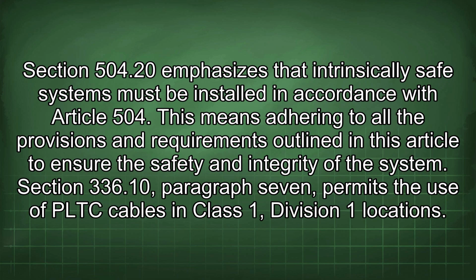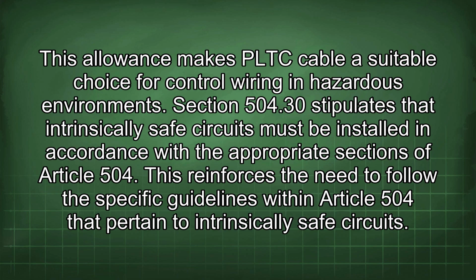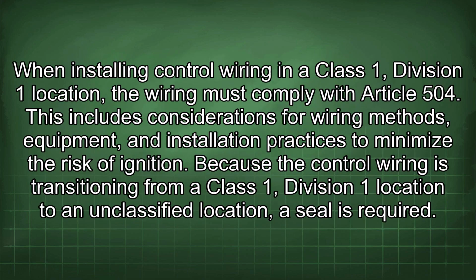Section 336.10, paragraph 7, permits the use of PLTC cables in Class 1, Division 1 locations. This allowance makes PLTC cable a suitable choice for control wiring in hazardous environments. Section 504.30 stipulates that intrinsically safe circuits must be installed in accordance with the appropriate sections of Article 504. This reinforces the need to follow the specific guidelines within Article 504 that pertain to intrinsically safe circuits. When installing control wiring in a Class 1, Division 1 location, the wiring must comply with Article 504. This includes considerations for wiring methods, equipment, and installation practices to minimize the risk of ignition.